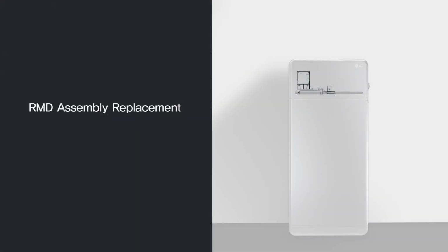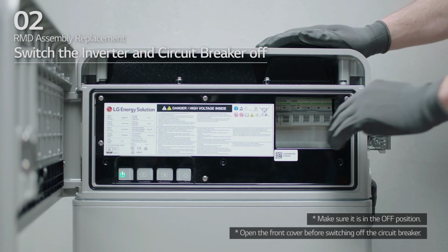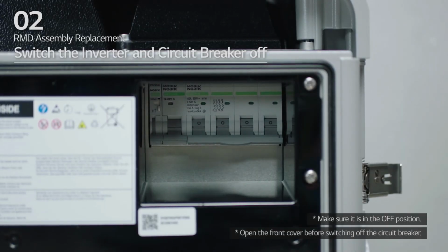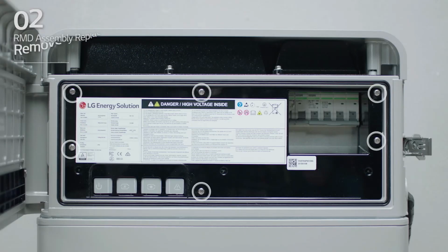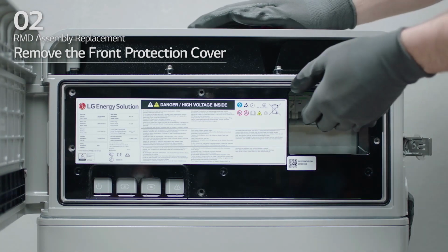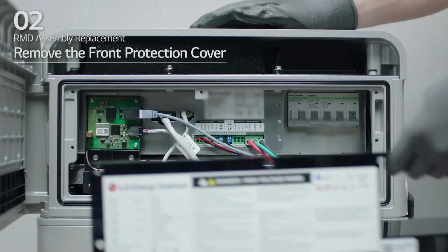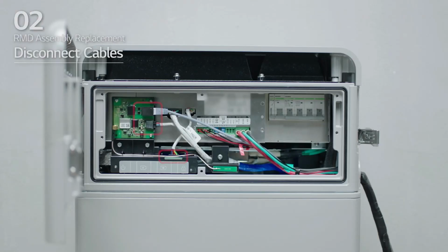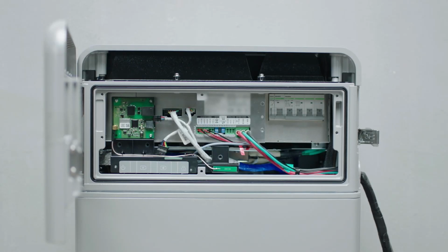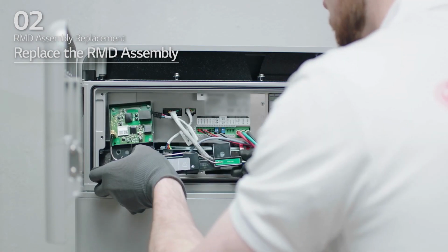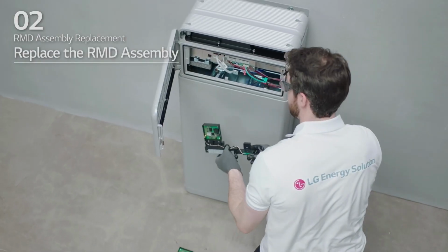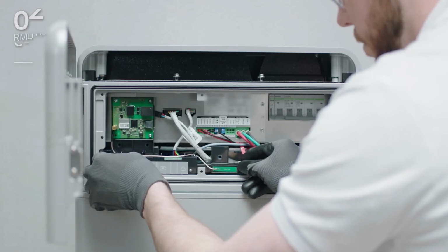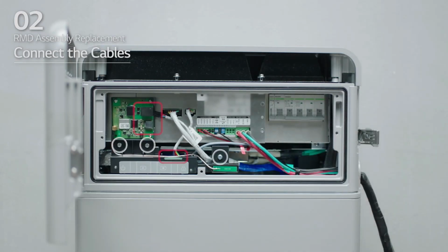2. RMD Assembly Replacement. Before replacement, switch the inverter and circuit breaker off. Loosen the 6 bolts to remove the front protection cover. Then disconnect the cables and loosen the 3 bolts. Replace the RMD assembly with a new one. After replacement, connect the cables and tighten the 3 bolts again.